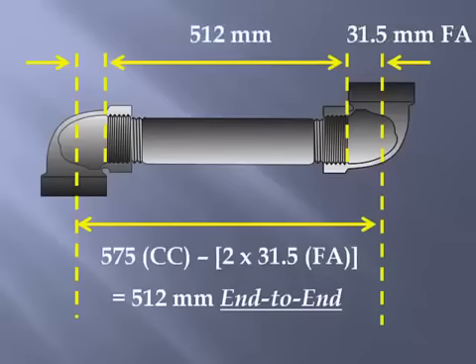To put it another way, a 512 millimeter end-to-end piece of inch-and-a-half pipe with two inch-and-a-half 90s threaded on to either end would create a center-to-center run of 575 millimeters.